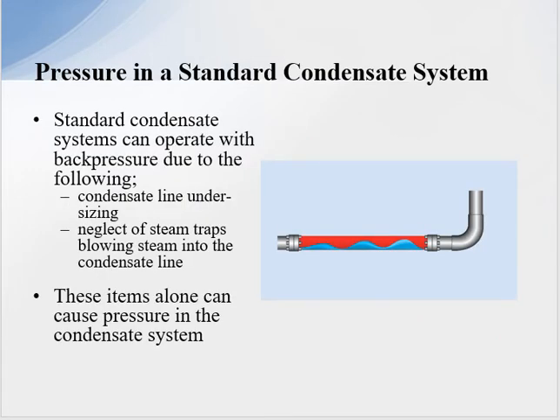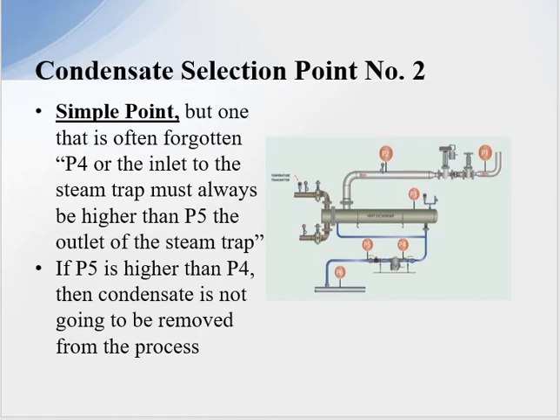Another factor we have to deal with in a standard condensate system is back pressure in the line. Unfortunately, all condensate lines operate with back pressure due to the following: undersized condensate lines where people aren't sizing the lines properly, and neglect of steam traps blowing steam into the condensate return line. That steam tries to expand sixteen hundred times and it's unable to, creating pressure in the return system. With those issues, there is a need in certain areas for condensate pumps. We have to look at it as a system.